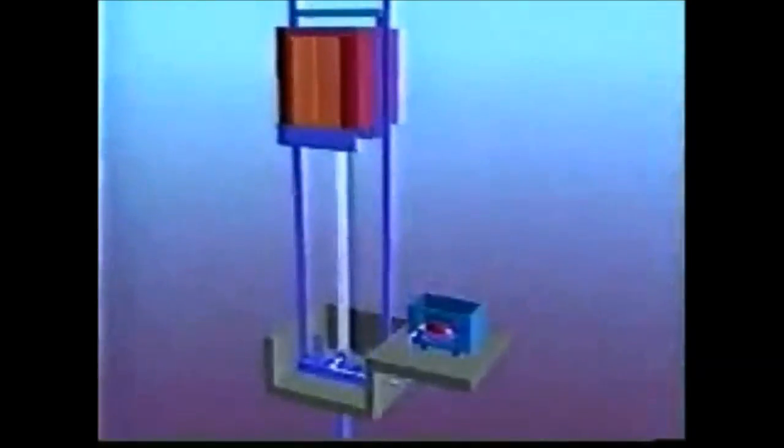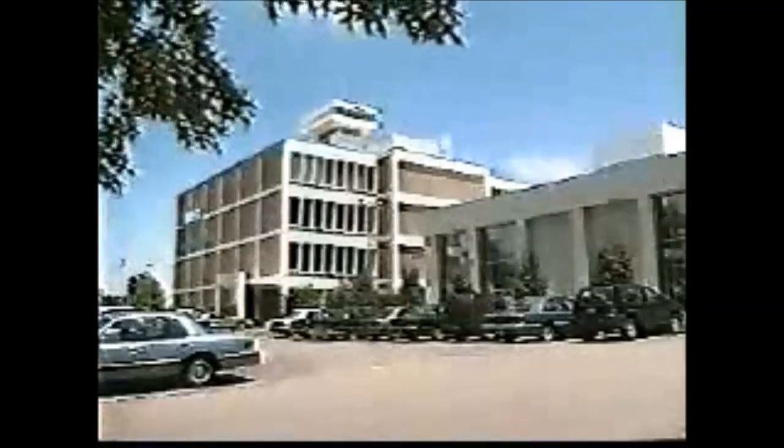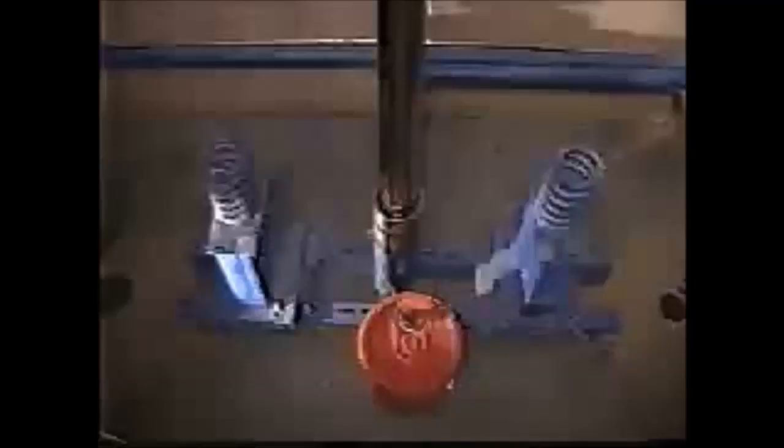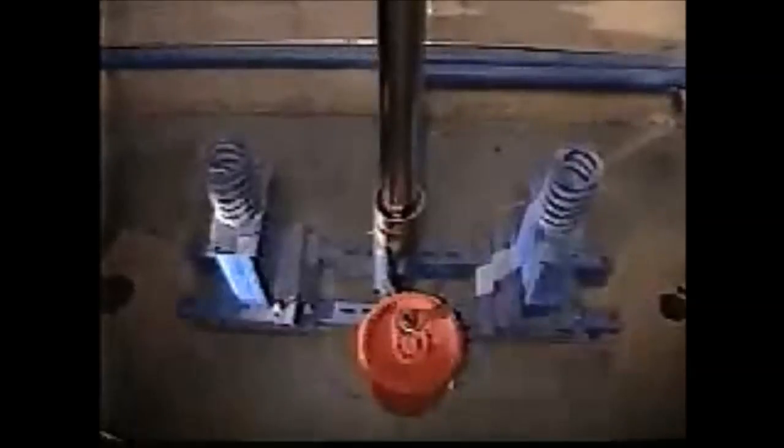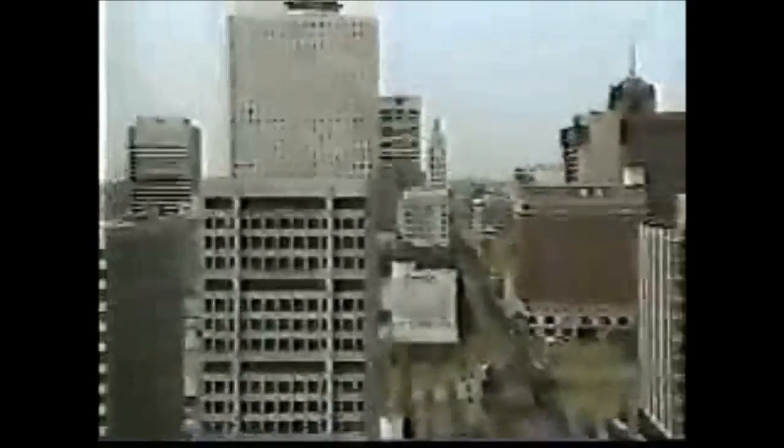Conventional hydraulic elevator jacks extend straight down into the ground as far as the elevator goes up. Digging for the jacks is expensive and difficult. The hydraulic elevator is used only in lower-rise buildings. The building doesn't need to be reinforced because the load is supported on the jack. This feature makes the hydraulic elevator a very popular design. The high-speed traction elevator has no limit on height and is suitable for a high-rise building.